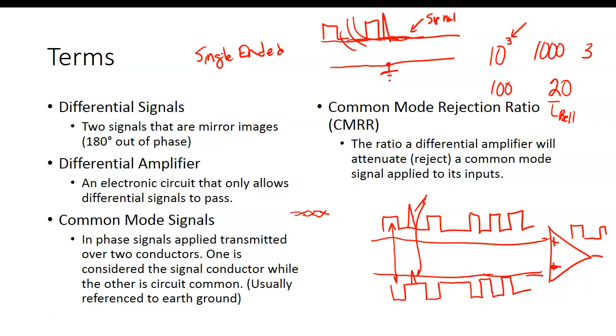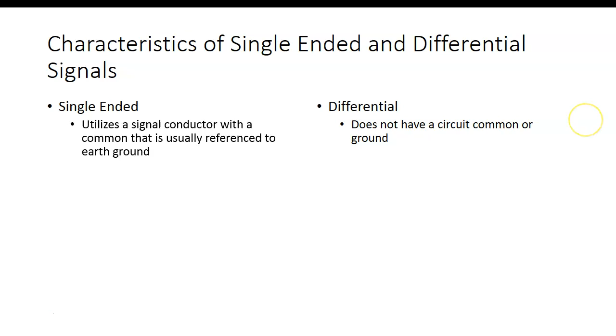So here's single-ended. Here's the advantage of single-ended: it utilizes a signal conductor with a common, and uses it for our reference to earth ground. Less expensive to implement, so you're still going to run into a lot of this. Very low common mode rejection ratio, so it's very susceptible to EMI.